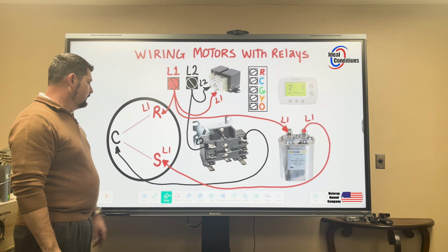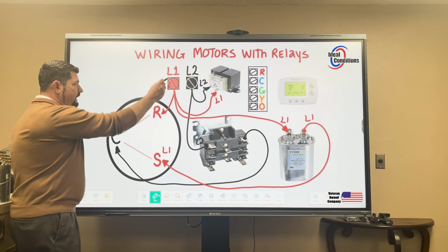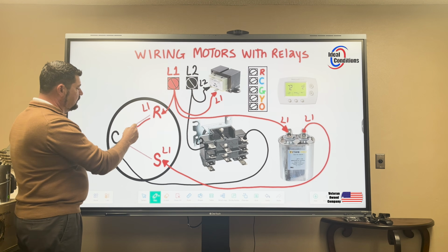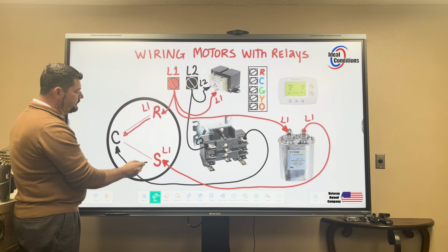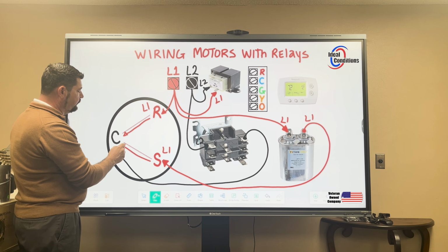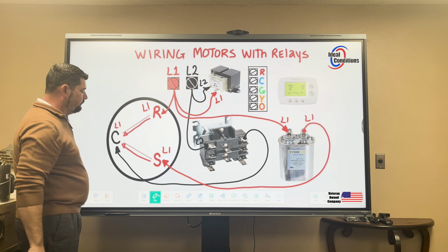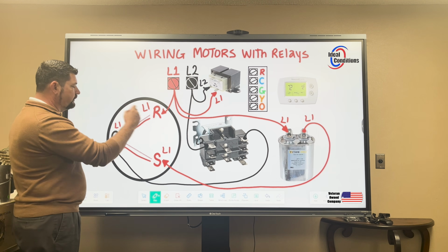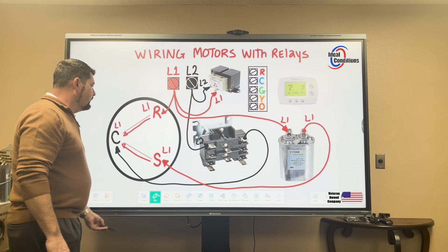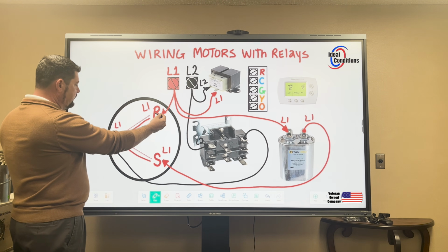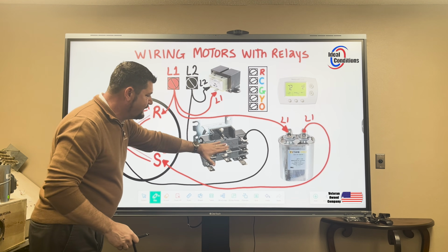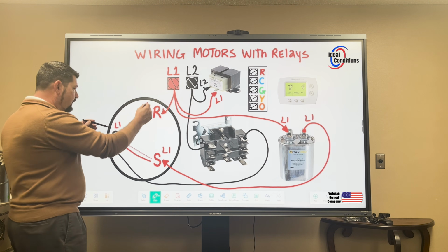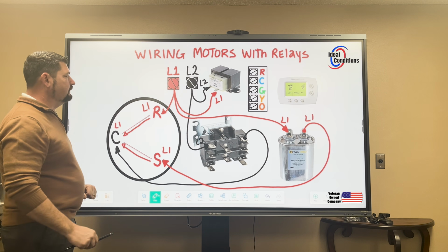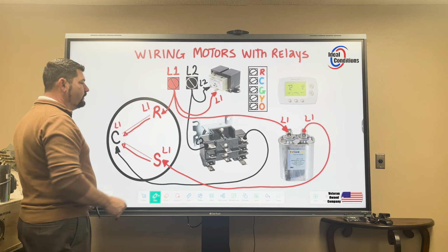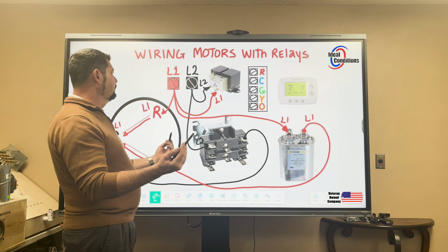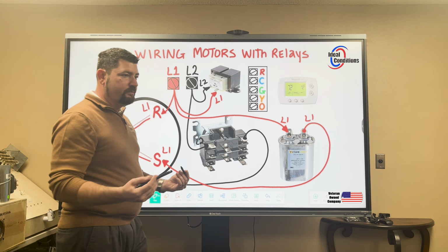All right, so if you look at the path of electricity, L1 comes through the run winding over to the common, and it sure does on the start winding too. So that means at this point in time, L1 is present all over the place. Now, if I took my meter and I wanted to see what I had between run and common at this moment in time, presently I would read 0, but if I were to touch it, I would get electrocuted. Now, the reason why I'm reading 0 here is my meter is reading no difference because you can't read a difference between L1 and L1.